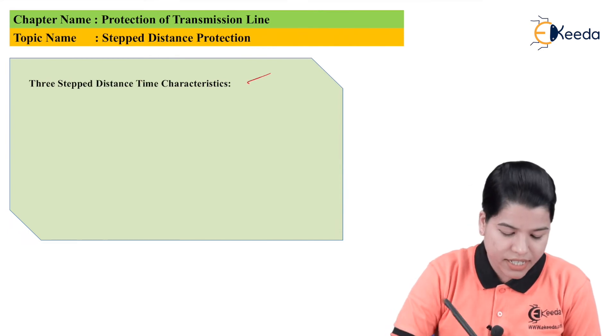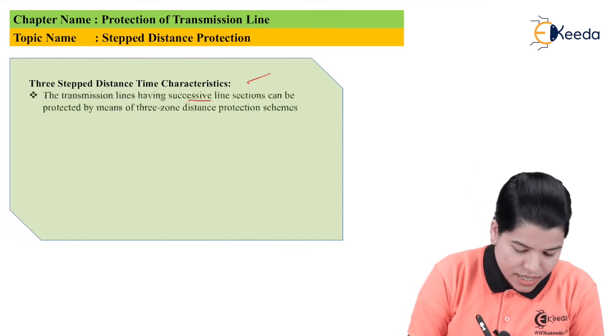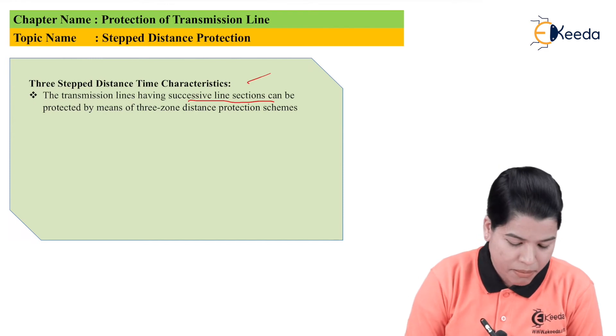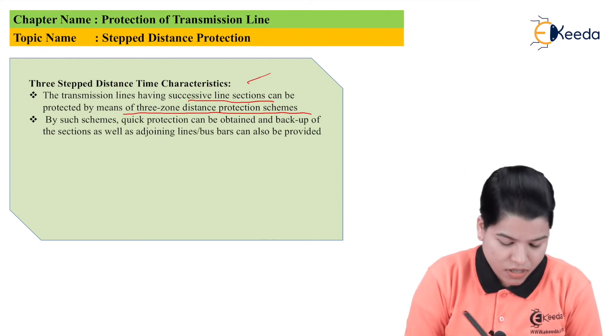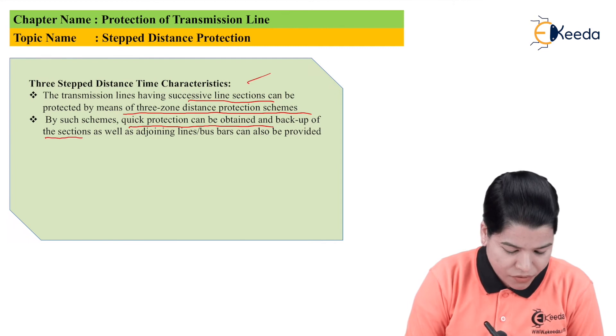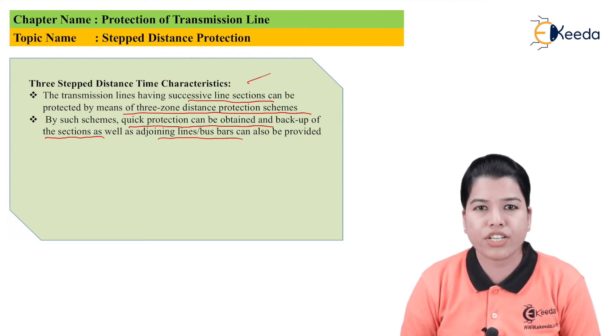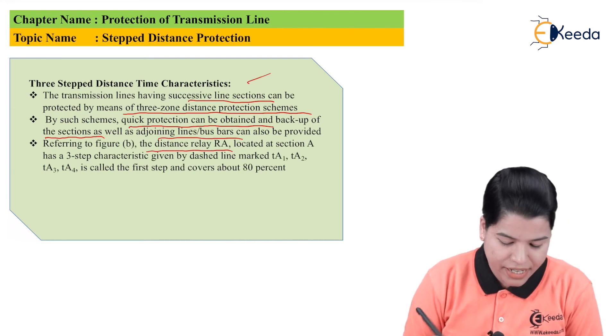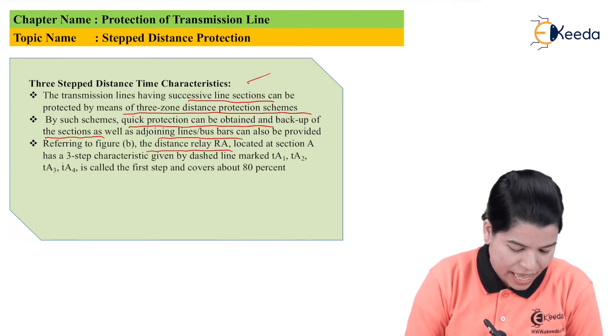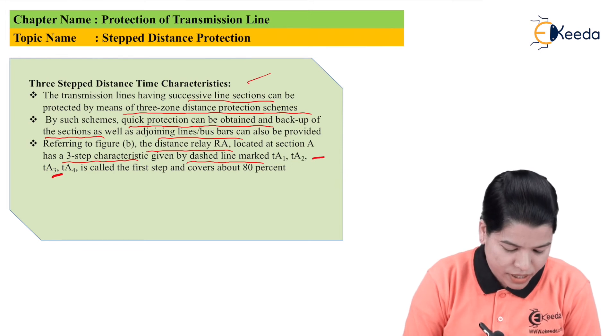Now let us study the three-step distance-time characteristic. Transmission lines with successive line sections can be protected by a three-zone distance protection scheme. This type of scheme provides quick protection and also provides backup for adjoining lines and bus bars, so both primary and backup protection can be provided. Referring to the figure, the distance relay RA located at station A has a three-step characteristic given by the dashed lines marked TA1, TA2, TA3, and TA4.